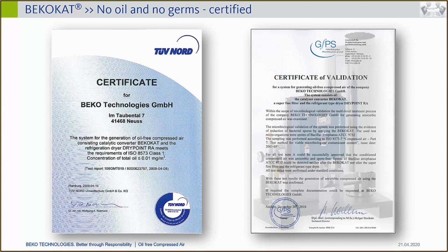But it's unnecessarily polluted with oil vapor if I have, for example, no BEKOKAT in between. It was an oil lubricated compressor just in between. Okay, an oil lubricated compressor. Yeah, it's a bit surprising that that was measured. Question is, how was it measured? Was it measured with the OCV? Okay, it was measured with OCV. So it's definitely an online measurement, and yeah, it's a bit surprising.